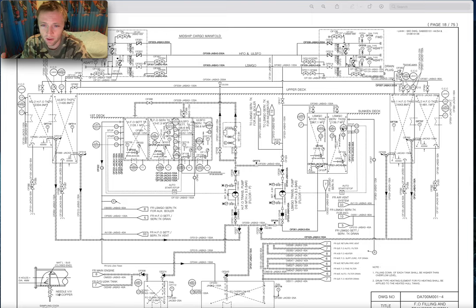We have some low level alarm switches and high level alarm switches, a level switch, which also must be tested, and normally this must be tested on a weekly basis, because it's really necessary that these alarms are working and will give us a pre-warning as engineers. We will be quicker to respond to this kind of alarms.